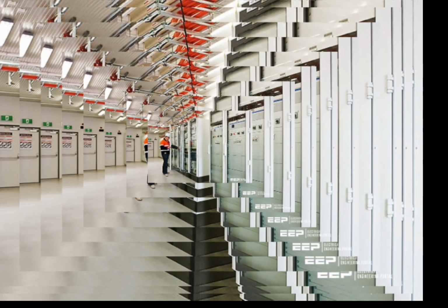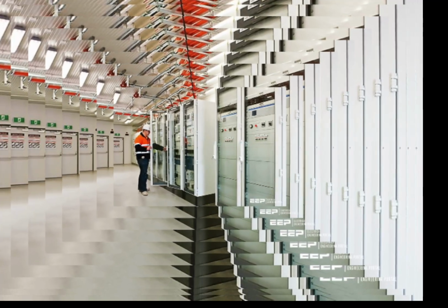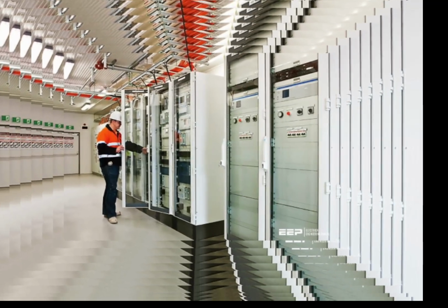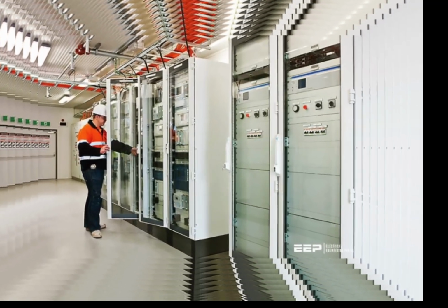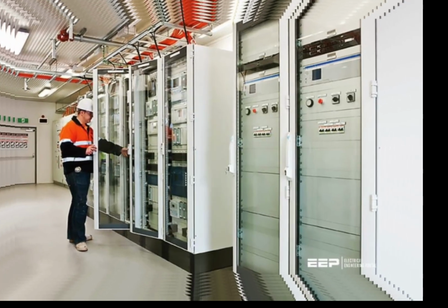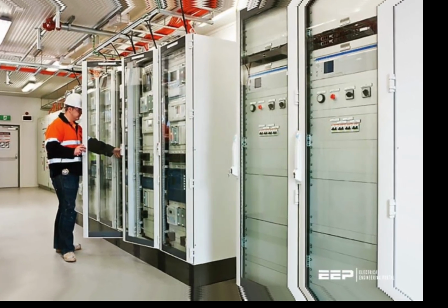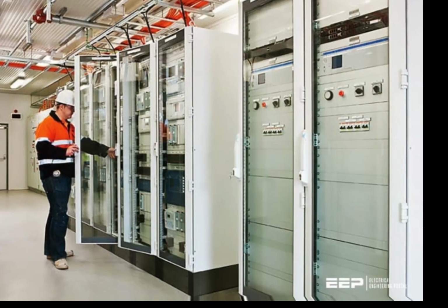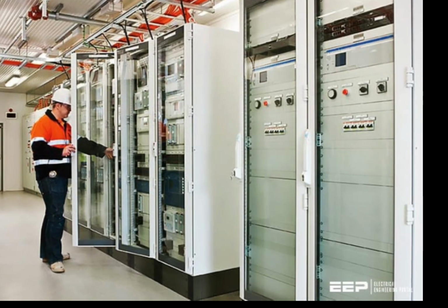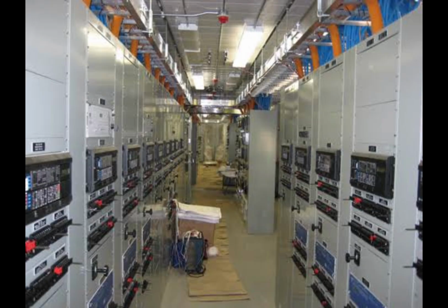If an AI data center campus in Ohio suddenly spins up a massive training run, pulling hundreds of megawatts of power, the SCADA systems register the voltage drop. Operators can remotely trigger motorized switches inside the substation, physically reconfiguring the bus bars to reroute power from a natural gas plant in Pennsylvania to cover the load. But this digital brain is the grid's second great vulnerability. While the physical hardware is protected by fences and cameras, the digital hardware is constantly probed by state-sponsored cyber threats.